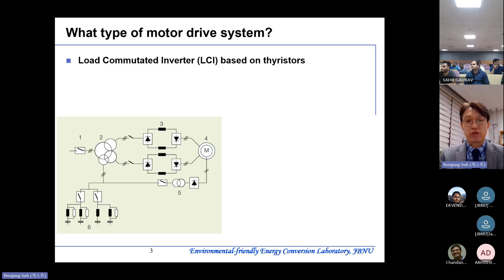This is a simple single line diagram. You have the Y and delta of the input transformer, and this is a tertiary transformer winding. You have parallel connected, 6 pulse load commutated inverters connected back to back. Using this configuration provides higher voltage than a single unit, and this is the rectifier system. This is an excitation system to supply the field current, and this is a tuned filter, because this system has a lot of 5th, 7th, 11th, and 13th harmonics, in order to filter those out.